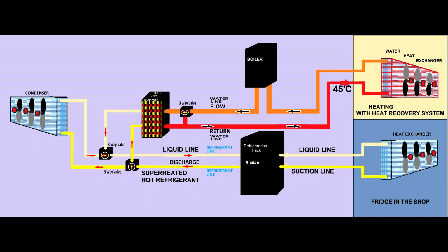And in this picture you will also see a boiler. That boiler is only there to control the temperature that goes into this plate heat exchanger. You will also be able to see it has a three-way valve which can divert the heating agent, I mean the water, in case we require a higher temperature, because we don't want to disturb the refrigerant pressure in the system. I will explain in more detail how this works.